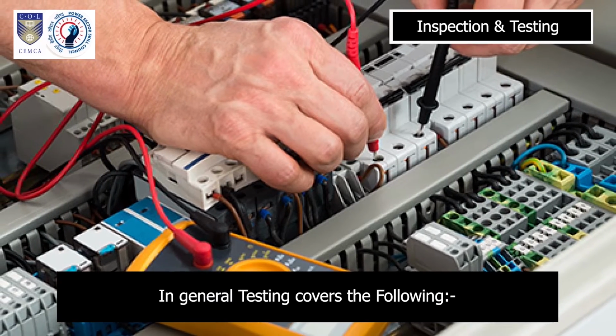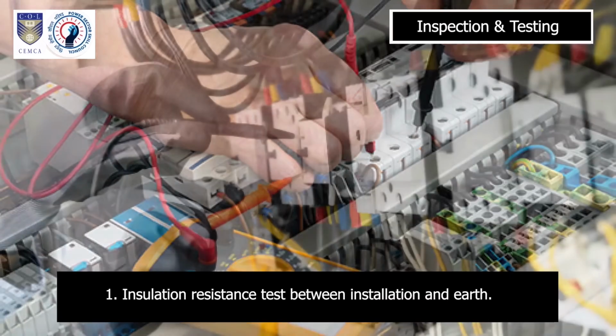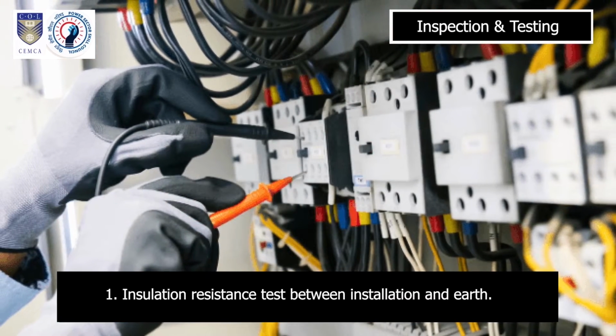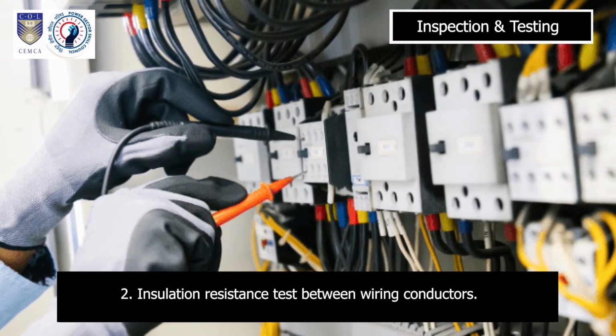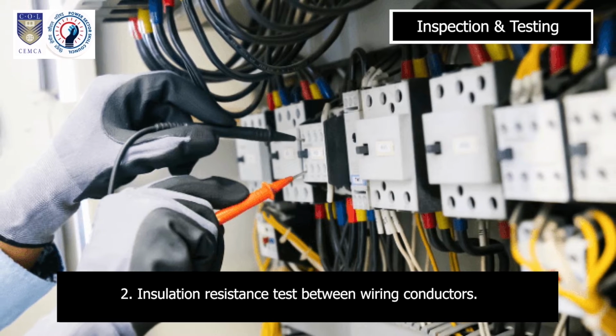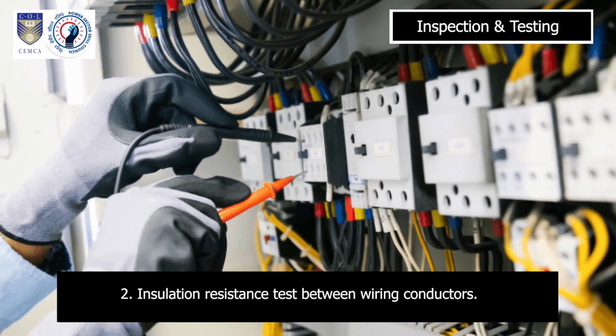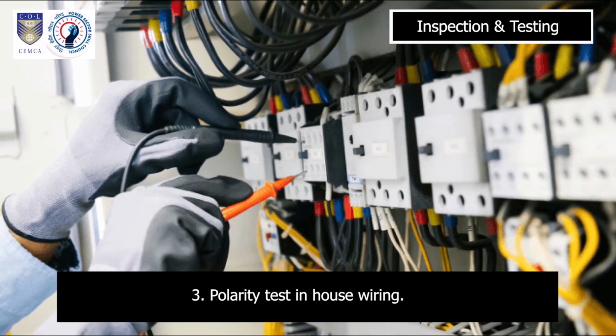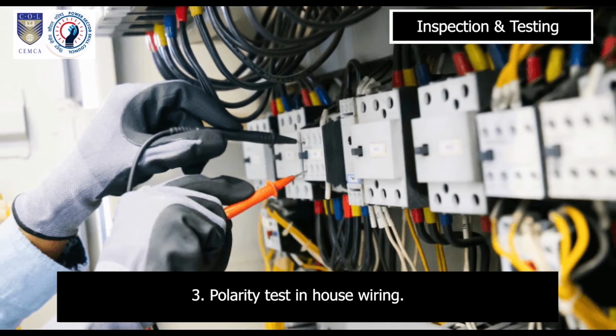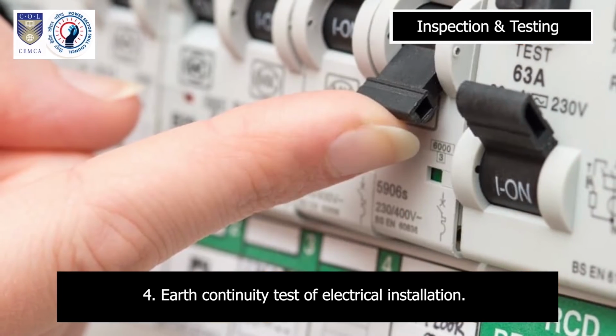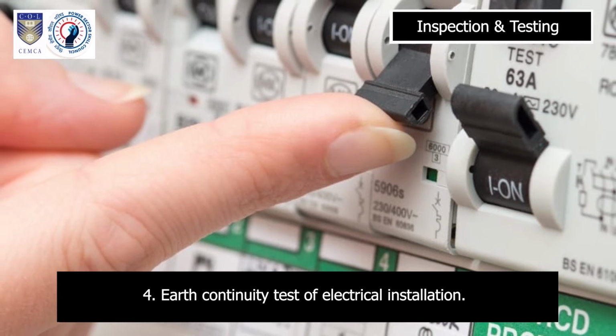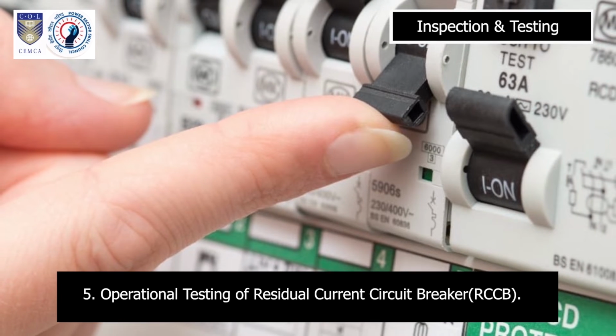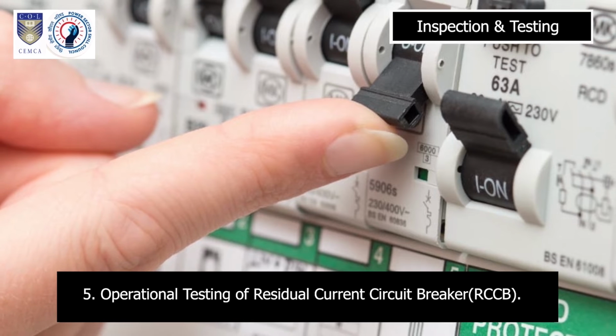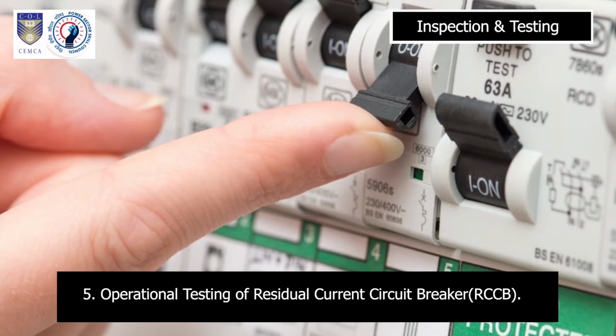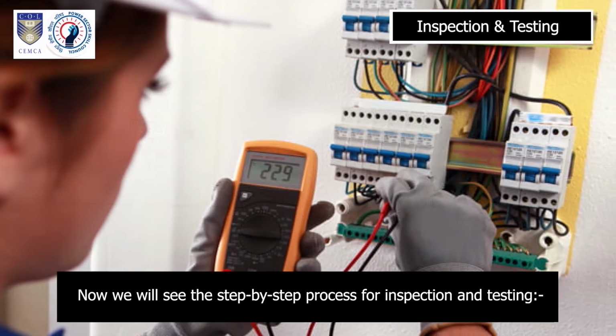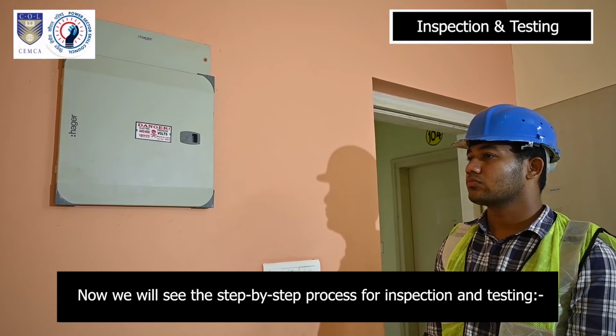In general, testing covers the following: 1. Insulation resistance test between installation and earth. 2. Installation resistance test between wiring conductors. 3. Polarity test in house wiring. 4. Earth continuity test of electrical installation. 5. Operational testing of residual current circuit breaker (RCCB). Now we will see the step-by-step process for inspection and testing.